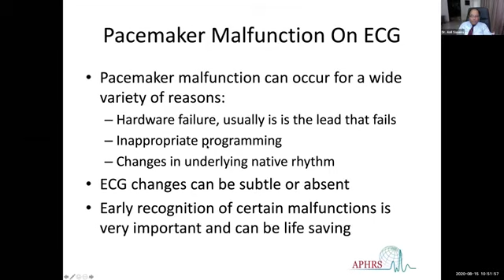Now, the problem with the pacemaker can be related to output failure, or there can be some failure to capture. The output may be there, but it may fail to capture. Otherwise, there can be sensing problems, and it could be both undersensing, when the pacemaker fails to sense a supposedly to be sensed intracardiac signal, or oversensing, where it is sensing something inappropriate, which could be an intracardiac signal, or it could be something outside the body. It could be some electromagnetic interference which the pacemaker senses and it starts malfunctioning.